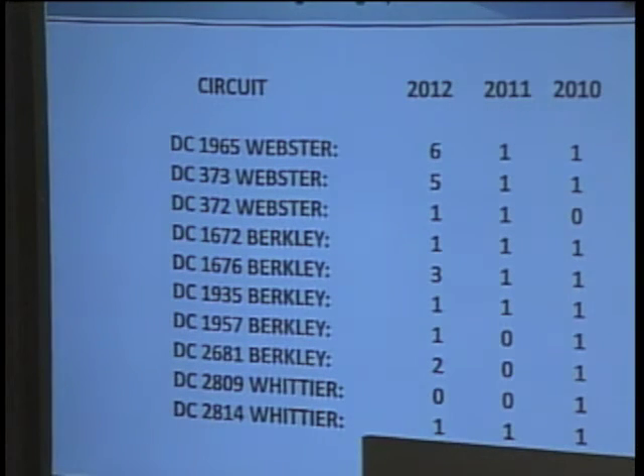So from a reliability standpoint, all of the circuits are very good, in my opinion. I know one outage isn't good for any of our customers. However, not all the portions of the circuits were out each time, but the majority of them had one, and those can usually result from a number of things. One of them could be trees, which is our most obvious condition, where we have wind or storm or lightning or ice, and the tree comes down into a portion of the circuit and you have an outage. Other things that cause outages would be drivers, where poles are hit by cars. Animals are consistently getting into some of our transformers and causing outages. And then there's always the unknowns. But fortunately, in this area, the reliability has been good from our statistical averages.